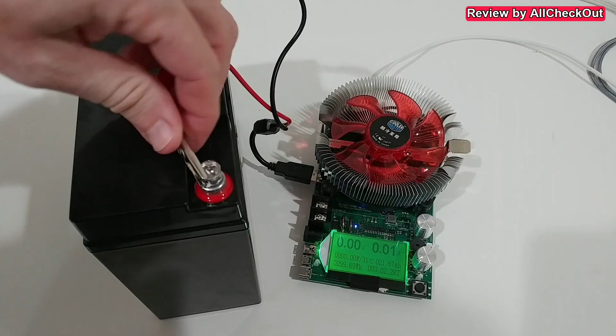I don't know if it comes back when we drop it to 0 and start it again. Maybe when I disconnect it and connect it again - let's see. Yeah, it's showing 10 volts again, so the BMS has reset inside, and we can maybe squeeze out a little more power, but I'm not pulling too much. You can see the voltage goes down pretty fast again: 96, 95, 93, 92, 91, 90, 89, and probably soon the battery will cut off.